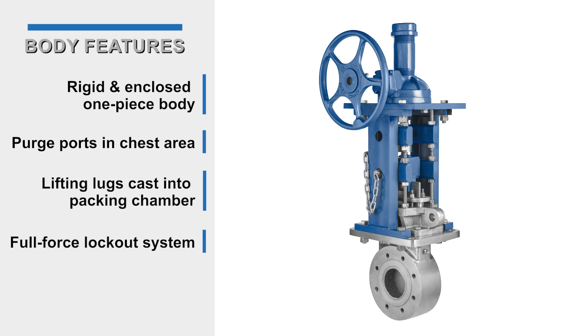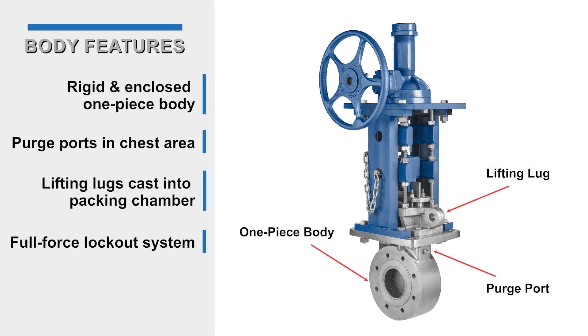KSV body features include a rigid and enclosed one-piece body to eliminate leak paths and discharge to atmosphere, purge ports in chest area to allow flushing of media from the valve interior, lifting lugs cast into the packing chamber to provide easy handling and installation, and a lockout system rated to the full actuator force with added safety factor.